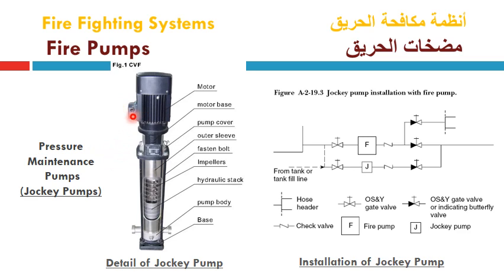And this is the power supply connection box to enter the cables to feed this electrical motor from the controller. The flow comes from the suction side and goes through the first impeller, then the second impeller, third impeller, fourth impeller, and so on until the last stage, and then it is collected and goes through the discharge of the pump from the other side of the suction.